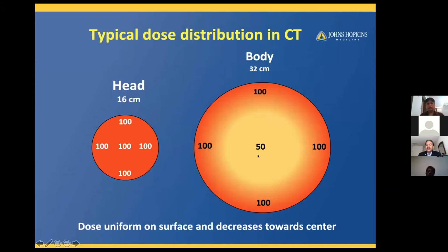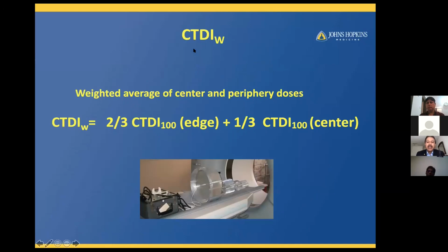This concept is included in the calculation of the computed tomography dose index. We introduce a second term, abbreviated CTDI weighted, the weighted average computed tomography dose index, given by this formula. It's 2/3 of the value measured at the edge of the phantom and 1/3 of the value measured at the center of the phantom. Again, the dosimetry is done by placing the phantom at the center of the CT gantry and doing one single axial slice at the center of the gantry, using a 100 millimeter chamber to capture all the radiation of the tails. Then by measuring at the edges and center, we can estimate what is called CTDI weighted.